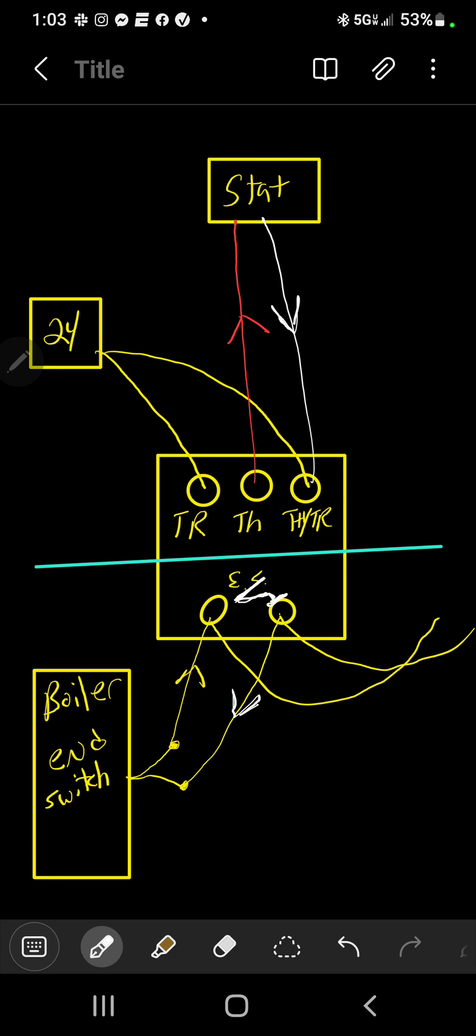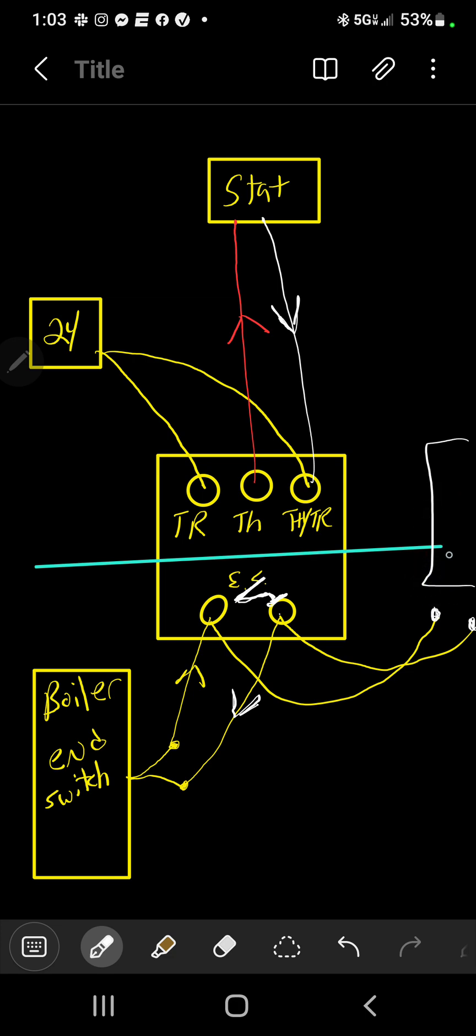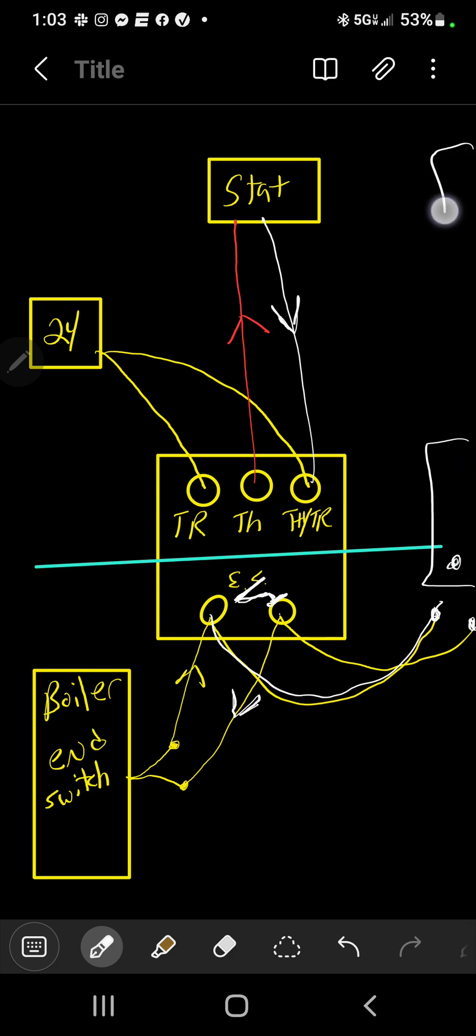Same thing over here. If you're on this end over here, if this zone gets a call, let's see if another zone valve over here. Same thing, your voltage is going to stop. It's going to come through this wire right here and it's going to stop. And then once this zone valve turns because it gets a call from the thermostat, once this turns, it now closes the switch here, sends the voltage back through here to this zone valve and then back to this zone valve and then fires up the boiler.